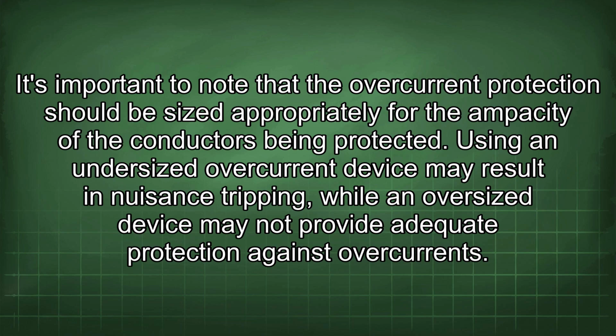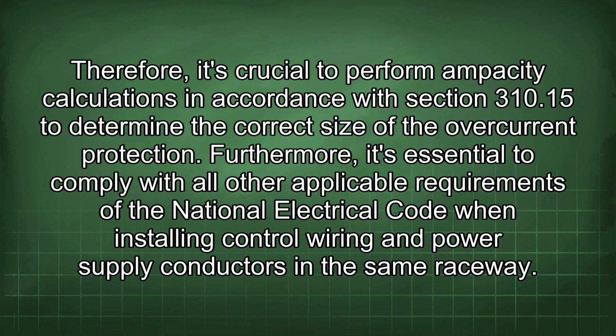It's important to note that the overcurrent protection should be sized appropriately for the ampacity of the conductors being protected. Using an undersized overcurrent device may result in nuisance tripping, while an oversized device may not provide adequate protection against overcurrents. Therefore, it's crucial to perform ampacity calculations in accordance with Section 310.15 to determine the correct size of the overcurrent protection. Furthermore, it's essential to comply with all other applicable requirements of the National Electrical Code when installing control wiring and power supply conductors in the same raceway.